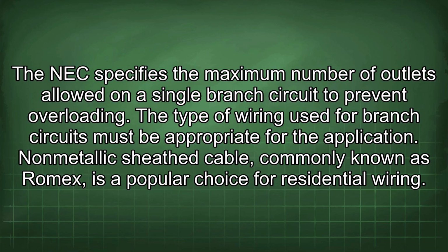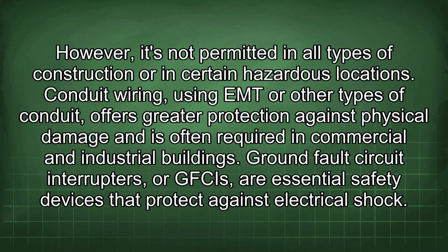Non-metallic sheathed cable, commonly known as Romex, is a popular choice for residential wiring. However, it's not permitted in all types of construction or in certain hazardous locations. Conduit wiring, using EMT or other types of conduit, offers greater protection against physical damage and is often required in commercial and industrial buildings. Ground fault circuit interrupters, or GFCIs, are essential safety devices that protect against electrical shock.